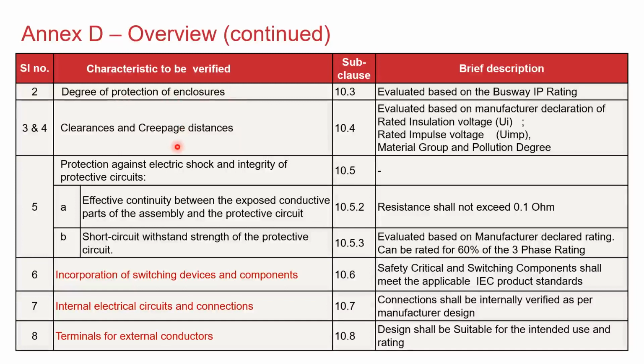Then we have the clearance and creepage distances. This is basically again determined based on the insulation voltage the manufacturer declares, the impulse voltage the manufacturer declares, the material group of the insulating material that's been used, and by default the pollution degree is taken as 3 for this determination. Then you have the test for electric shock and integrity of protective circuits.